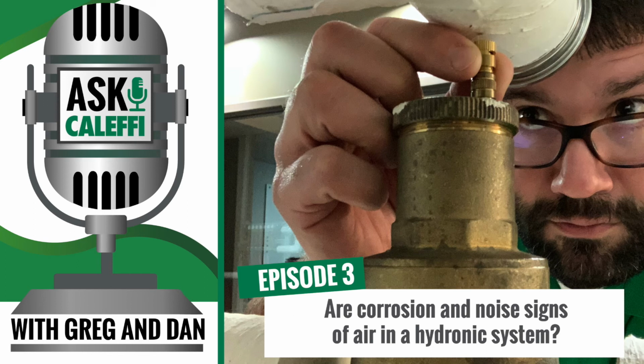That might get you in trouble on a job, because you look at a lot of these boilers and you can have a 200,000 BTU boiler coming out in 1 inch, coming out of the boiler. That doesn't mean you're going to pipe 1 inch to it. That just means what it's leaving that heat exchanger at.